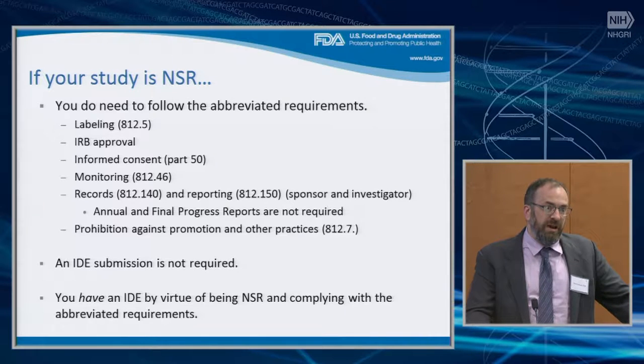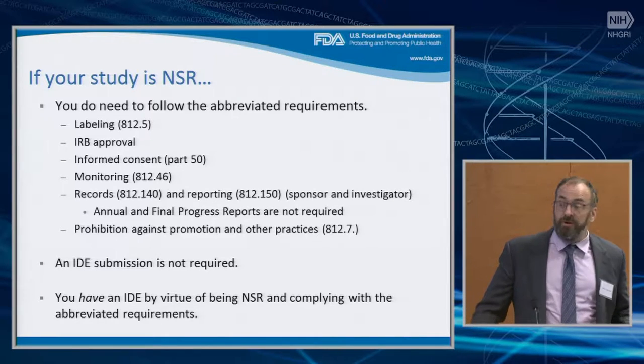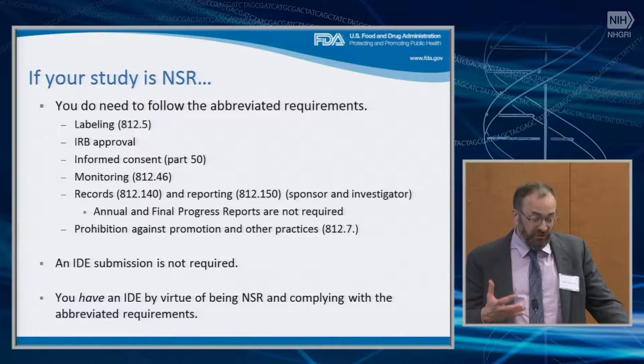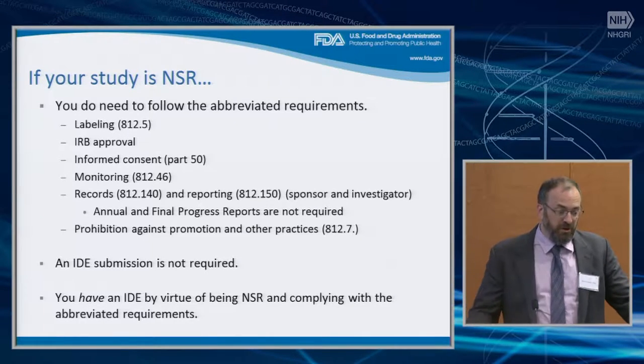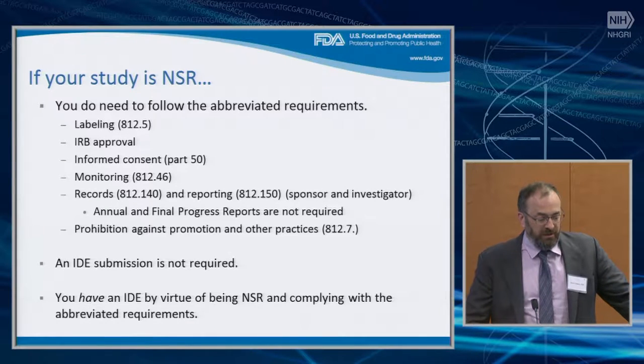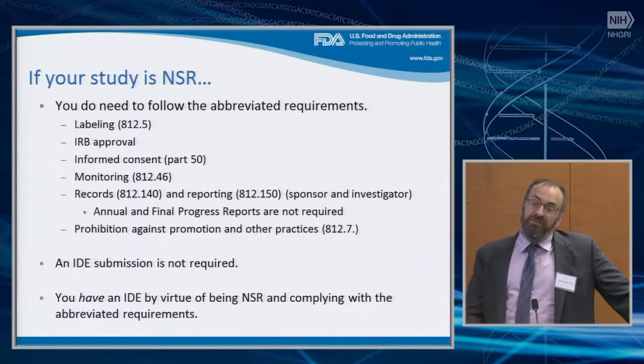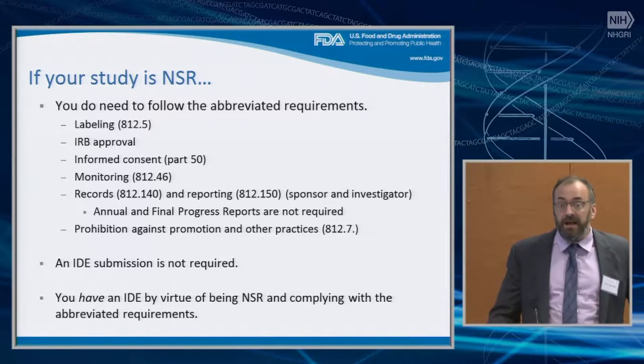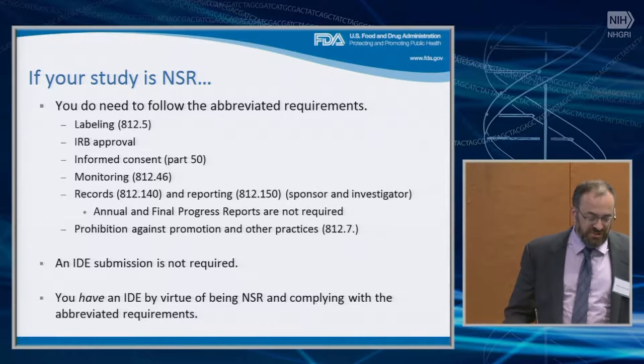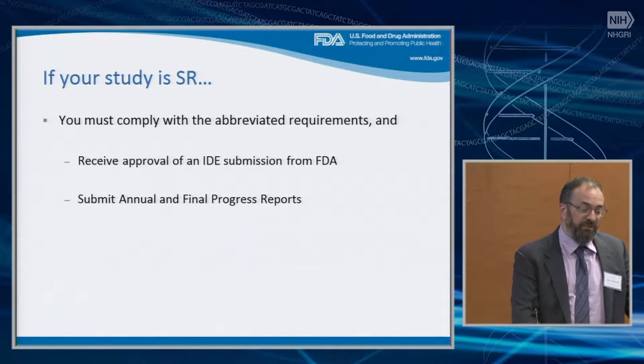In the case of in vitro diagnostics, adverse events can be very difficult to identify, so often you won't even identify adverse events related to the test. We don't need annual and final progress reports either in that case — mostly it's internal record keeping and a couple of other things. One important point: it's not that you didn't need an IDE, but once you've followed the abbreviated requirements, you are considered to have an investigational device exemption. That still means you're covered under the regulation and do have some requirements.